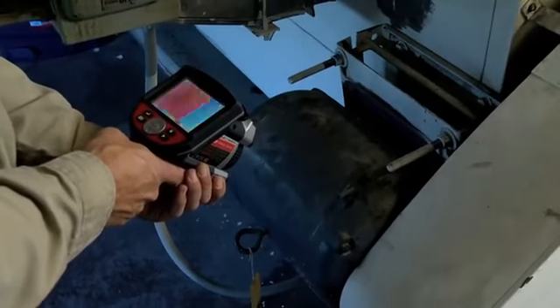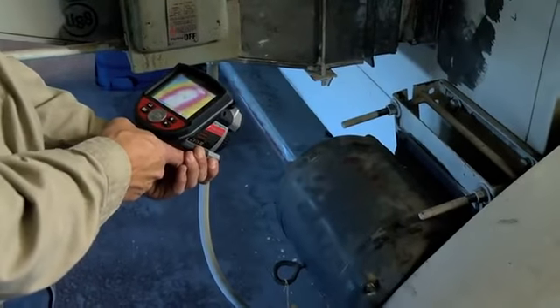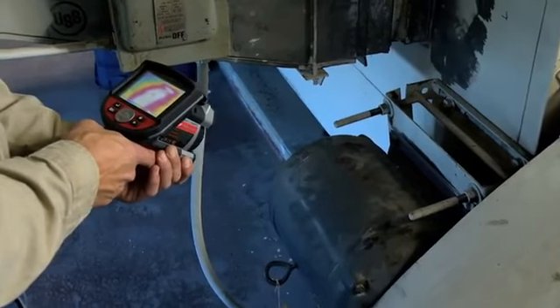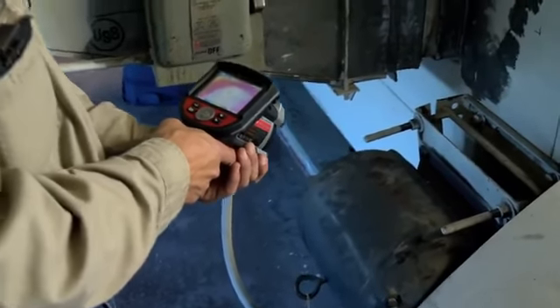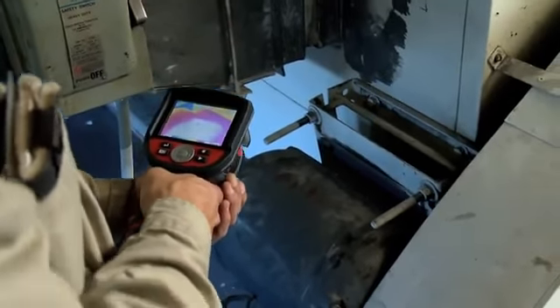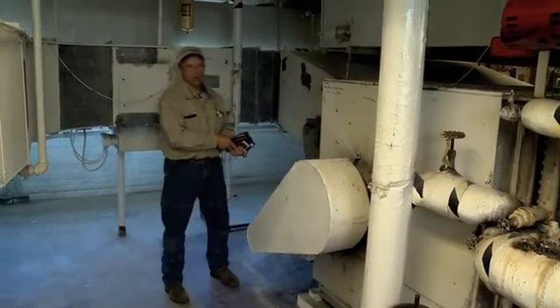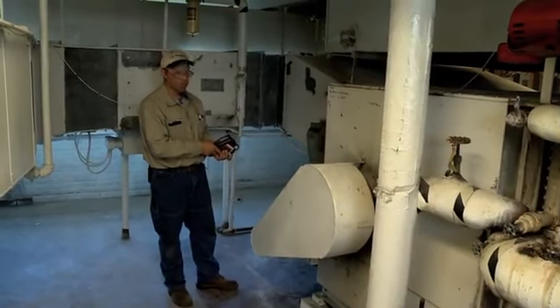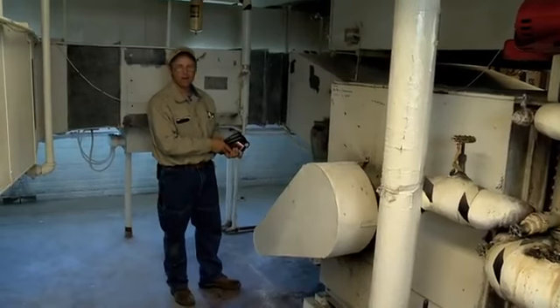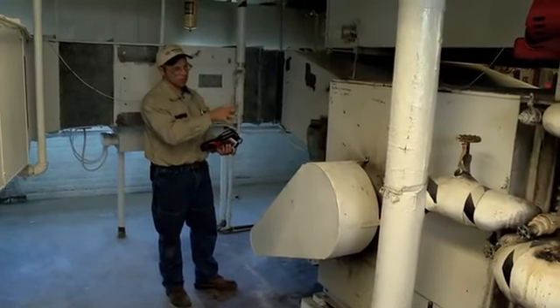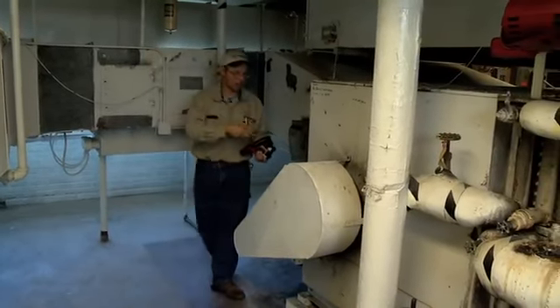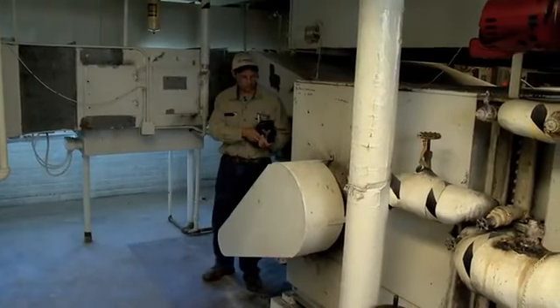Right now the motor is running at about 106 degrees. I can check the front and the back of the motor. There's bearings on both sides, they both seem to be fine. If the motor was running hot, we would be looking for electrical problem or bad bearings in the motor. We could also be looking for a problem with the fan bearings themselves.